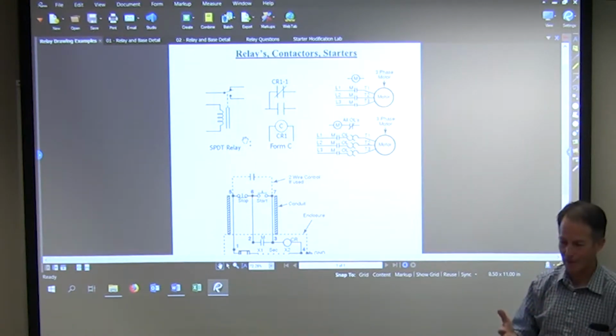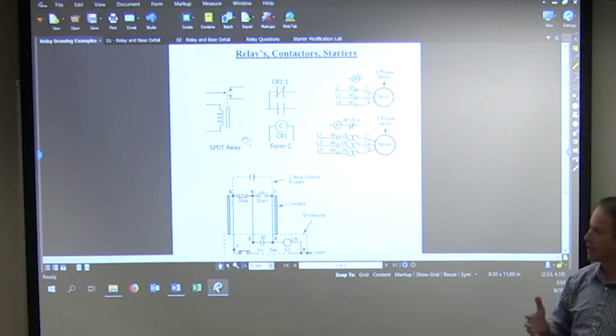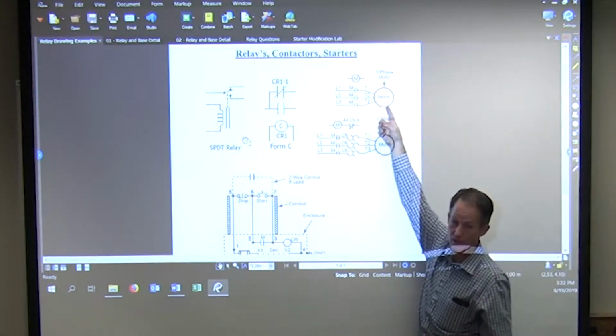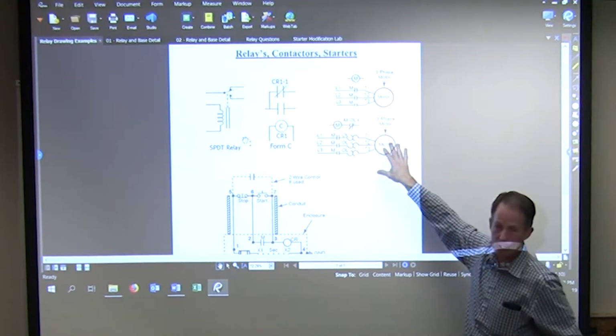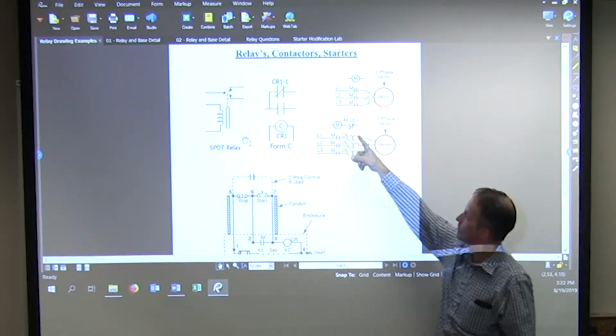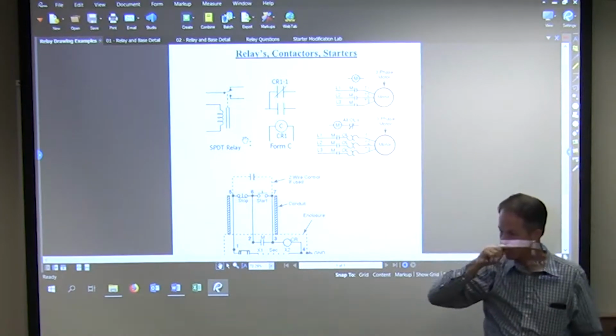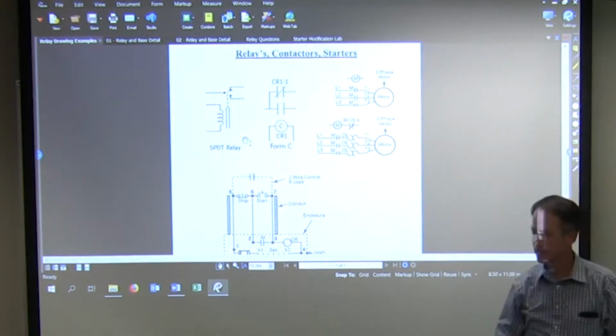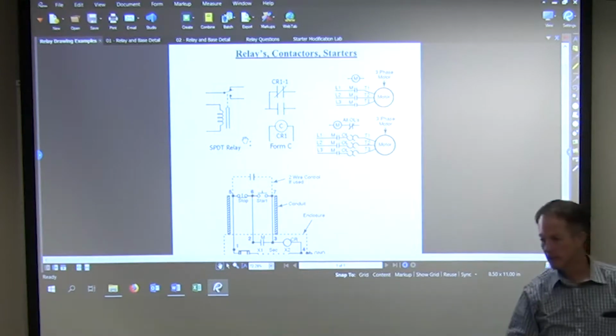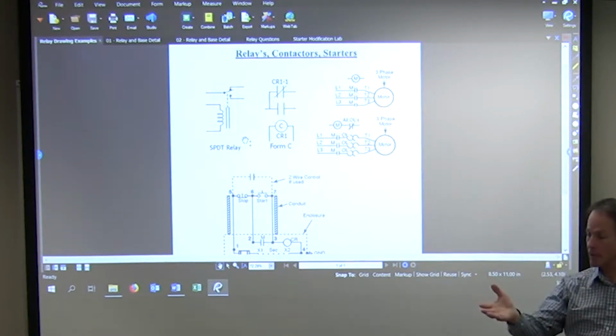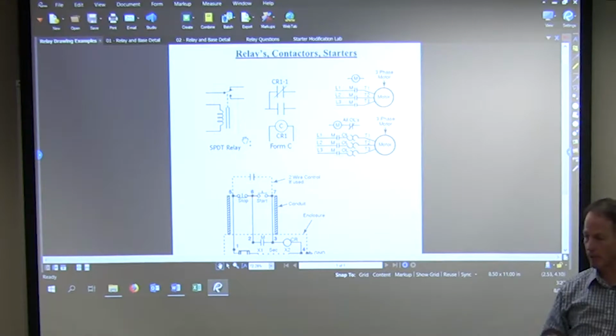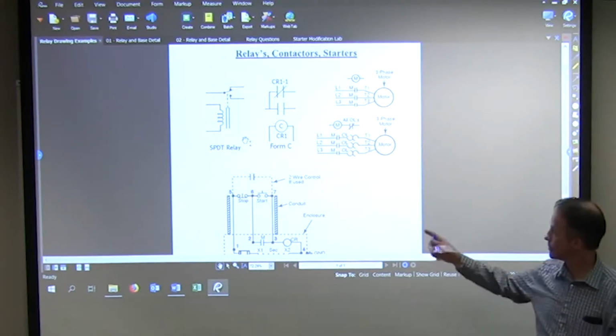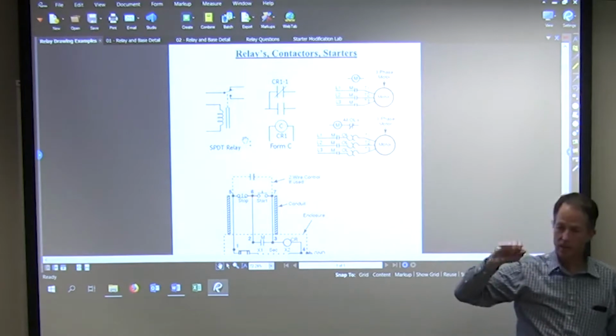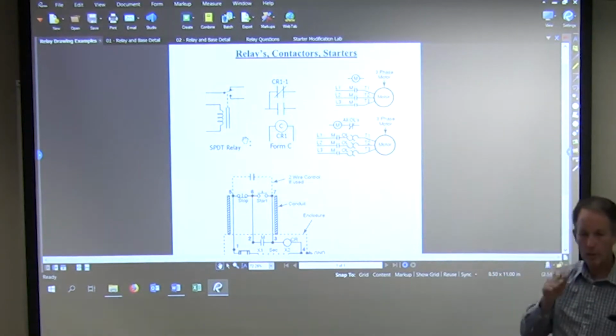We don't want that to happen. Motors don't last long, especially if we have this kind of a starter, right? If we have a contactor, what do we gain? Get overloads in there. You still have internal overloads on that three-phase motor. They do. It's going to kick in and kick out, you won't hear it. It's still going to short-live the motor, right? It can really damage it, in some cases it can ruin it totally. Especially if it's a solid state internal overload, something like that, is what they've gone to now, no longer it clicks on. Right. So, okay, but these overloads here are designed to protect the motor, people, or both.